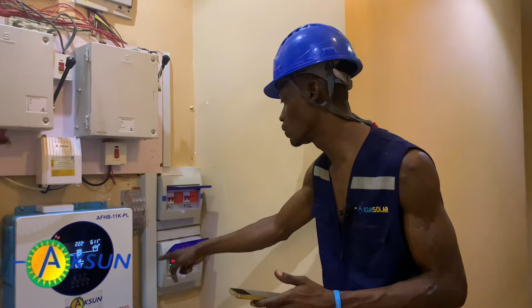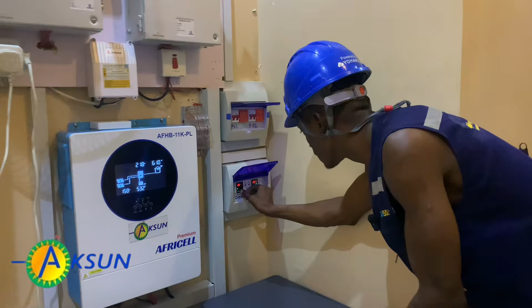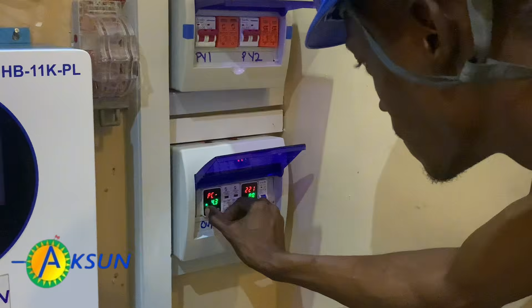So you define whatever you have by your output voltage, 220. I have 45 amps, which means the maximum load our load can draw from this system is 45. So you set 45 there. So that's modified. So I save, and I confirm again. That's that. So now for our grid, we're also going to do the same settings.